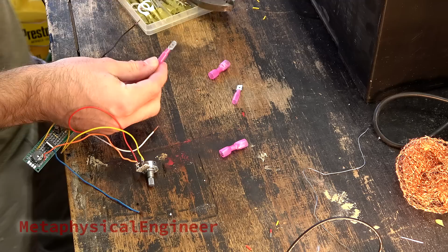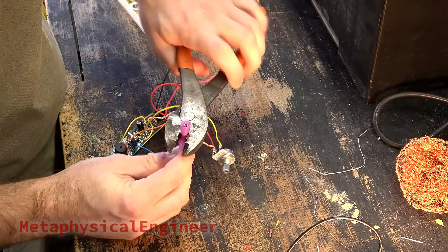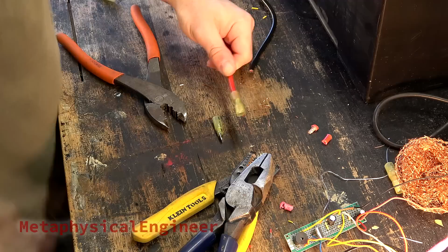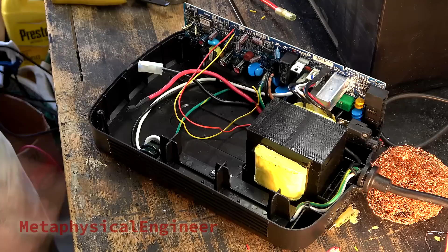Putting crimp spade connectors so the fan driver can be unhooked easily. And prepping these 8-gauge supply wires. Had to trim a few strands to fit the connectors. 10-gauge of wire would be suitable here, but I'm upsizing a bit on purpose. Every fraction of a volt dropped will eat into the inverter's efficiency and its runtime. Terminals on the UPS are slightly loose as well, so those get swapped.